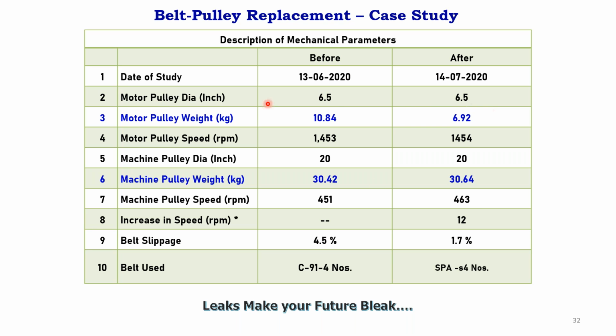The pulley diameter is not changed, but the pulley weight is slightly changed. Then automatically the load on the shaft will be reduced. Because of that, the current and power will be reduced. Of course, the motor speed was also measured, and the machine speed is slightly improved. Because of that, we have an improvement in productivity also.